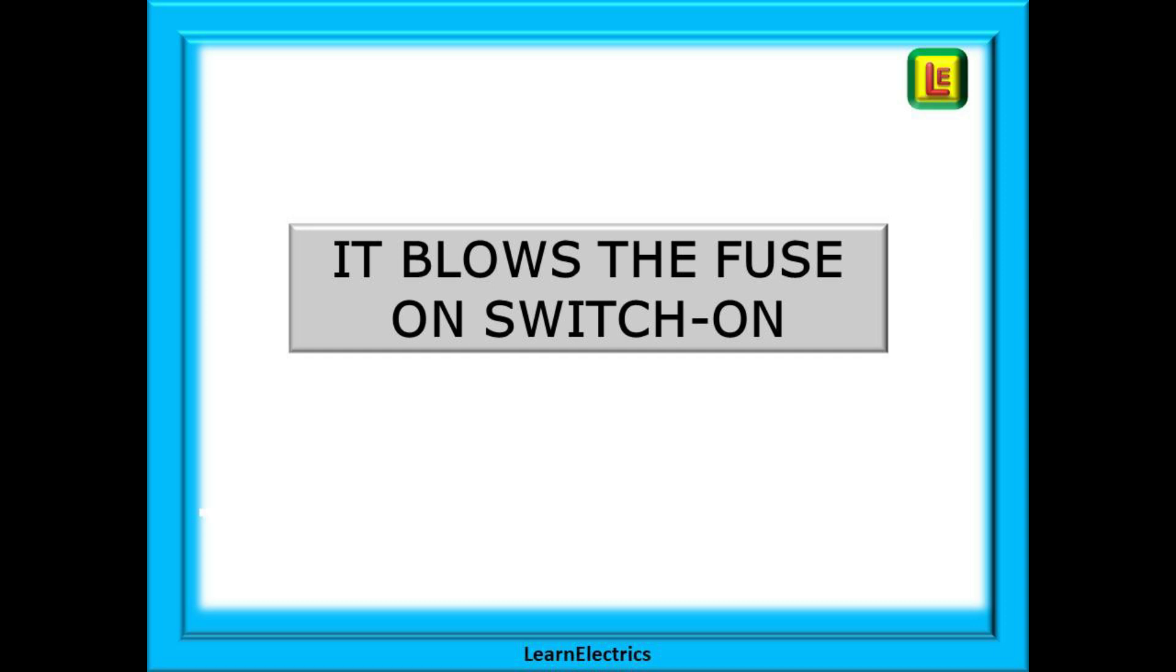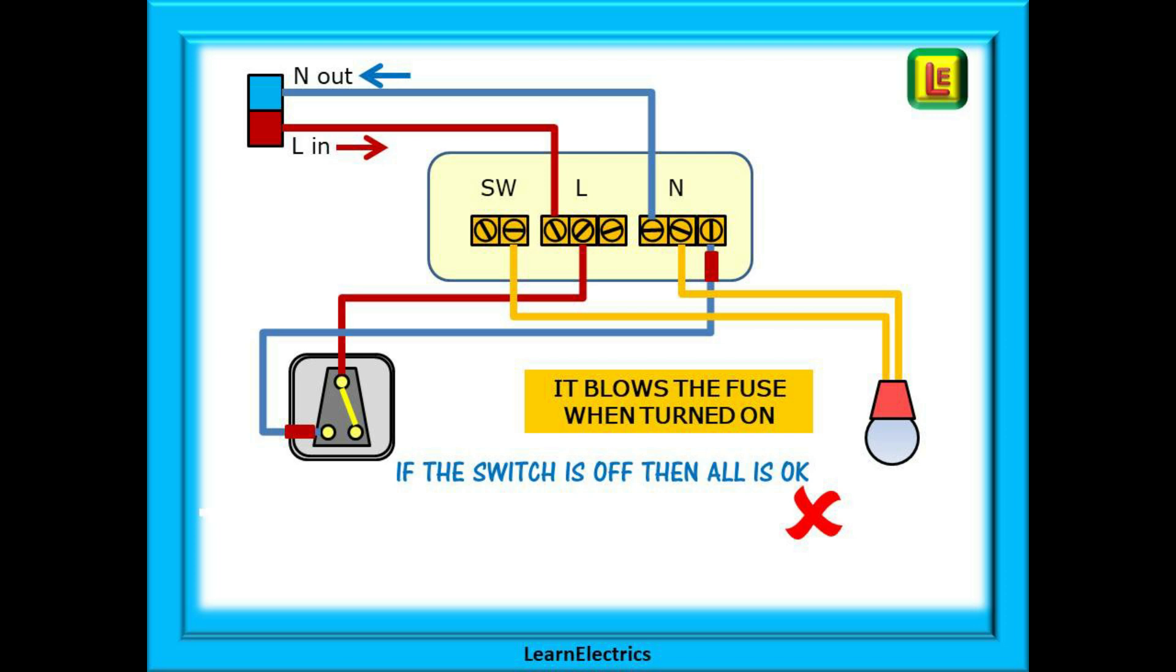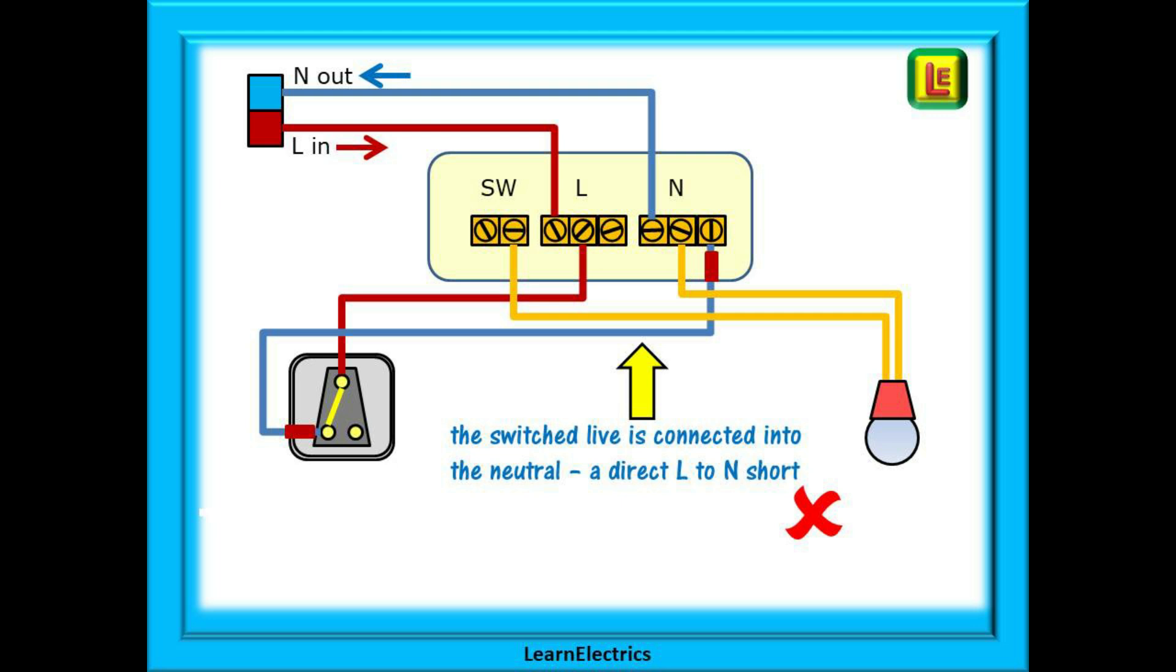Another common problem after decorating is this one. The customer tells you that every time they switch the light on, it blows the fuse. They are usually quite desperate at this stage as they now have no lights in the house. If the switch is off, the breaker is okay. But when they switch it on, bang! All the lights in that part of the house go out. So what has happened and how do we fix it? The customer will tell you that they've been decorating and they've put the wires back themselves. To the customer, all blue wires are neutral and should all go together in the neutral block. But we know different, or should do.